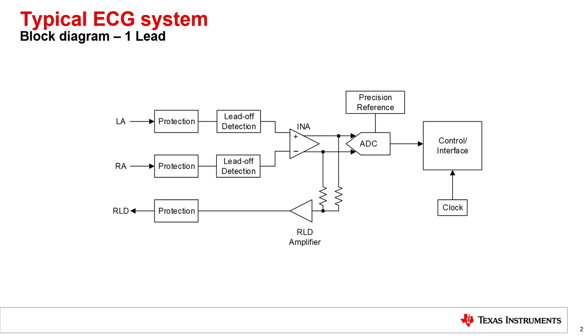Following each electrode, there is typically some protection circuitry that is needed to isolate the patient from fault currents. It also serves to protect the ADC subsystem from overvoltage events, such as a high voltage shock from a defibrillator. Most applications then require some form of leadoff detection to verify that the electrodes are still connected to the patient and to monitor the connection quality.